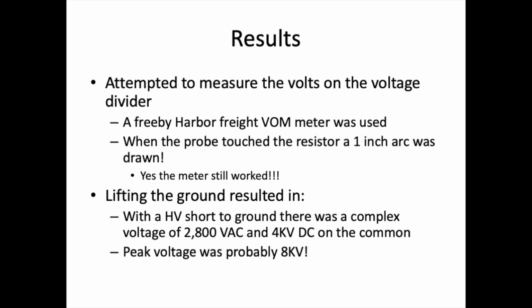But anyways, lifting the ground here, with the high voltage shorted to ground, there was a complex series of voltages. Essentially we had the DC voltage, which was about 4 kV, plus on top of that was another 2800 volt AC with a peak voltage of about 4,000 volts too. So at that point we had roughly 8,000 volts peak.